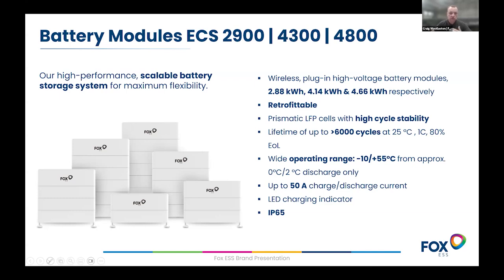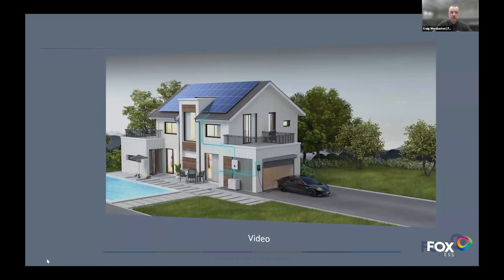There is obviously an exception. If you have a very small stack, a 2-battery stack, the rate's going to be slightly lower and might fall slightly below the maximum output of the inverter itself. Hopefully that's clear, because it is a question we get asked, and it is a calculation you have to make depending on your setup.